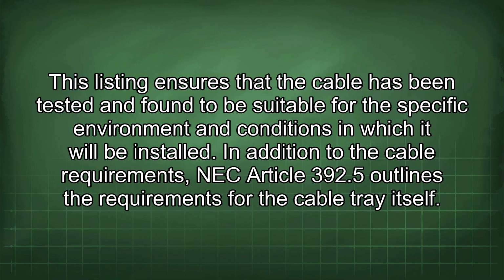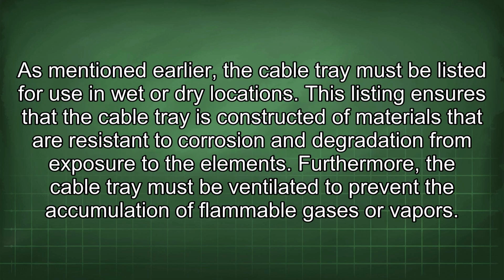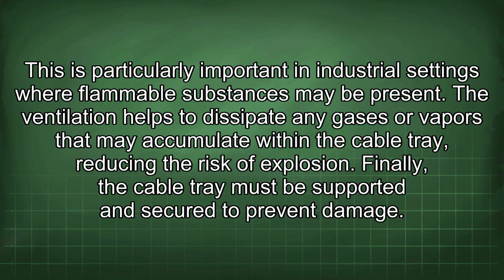In addition to the cable requirements, NEC Article 392.5 outlines the requirements for the cable tray itself. As mentioned earlier, the cable tray must be listed for use in wet or dry locations. This listing ensures that the cable tray is constructed of materials that are resistant to corrosion and degradation from exposure to the elements. Furthermore, the cable tray must be ventilated to prevent the accumulation of flammable gases or vapors. This is particularly important in industrial settings where flammable substances may be present. The ventilation helps to dissipate any gases or vapors that may accumulate within the cable tray, reducing the risk of explosion. Finally, the cable tray must be supported and secured to prevent damage.